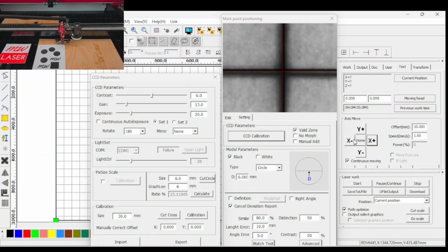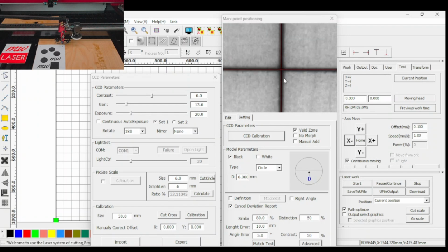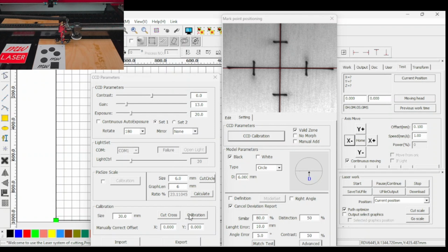If I want to fine tune it even more and say, well, 1 millimeter a second is too much, or I want an offset of 0.1 of a millimeter, I could then turn the continuous movement off and I would move only 0.1 of a millimeter in each direction. So you can fine tune that and get it as close as you can to the center of that cross. Once you've done that, you press on the calibration and that will then pop up and say success.